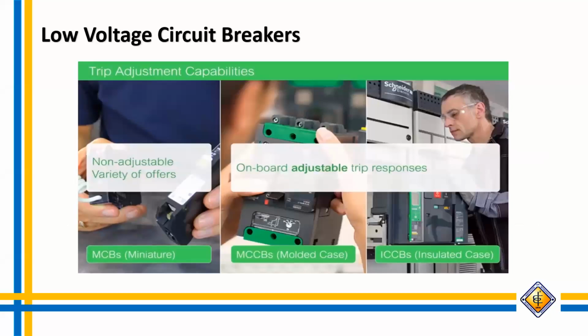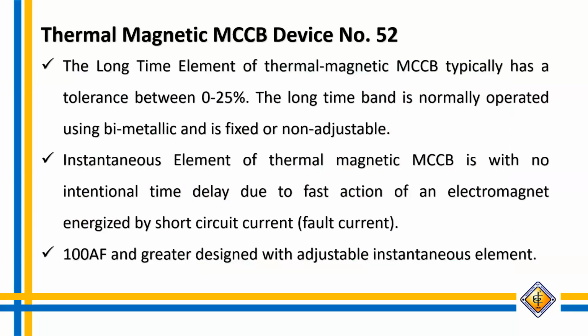As you can see here, this is the trip adjustment capabilities of the low voltage circuit breakers. We have the MCB, also known as the miniature circuit breaker. This is the non-adjustable type, so it is fixed. We also have the MCCB and the ICCBs, which have onboard adjustable trip responses.